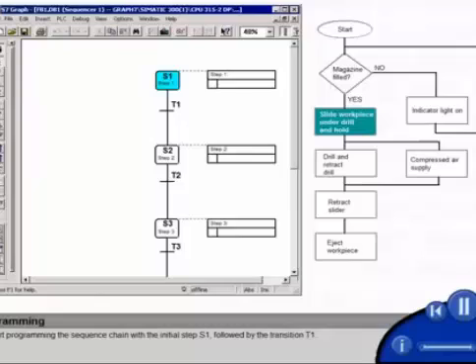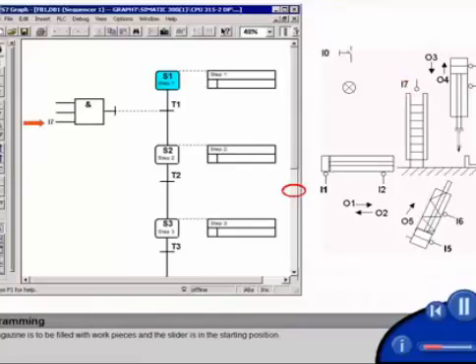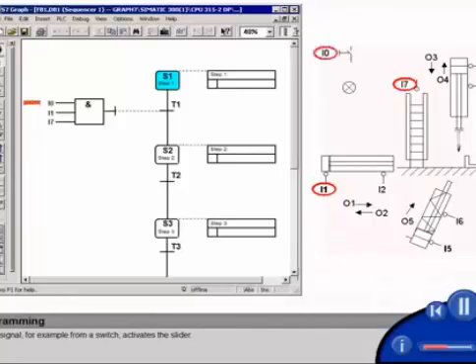We start programming the sequence chain with the initial step S1, followed by the transition T1. As a first action, the workpiece is to be moved under the drill. To start this action, we created the following AND logic operation as transition T1. The magazine is to be filled with workpieces, and the slider is in the starting position. A start signal, for example from a switch, activates the slider.